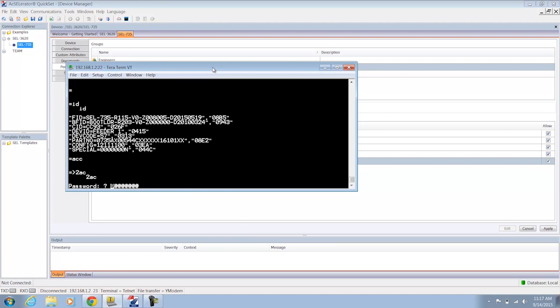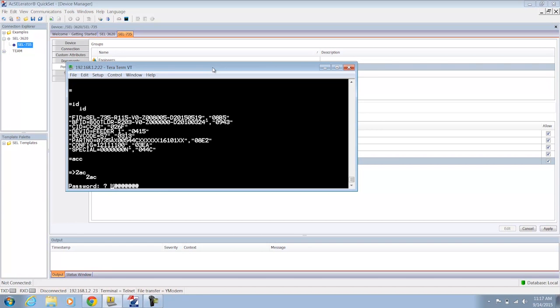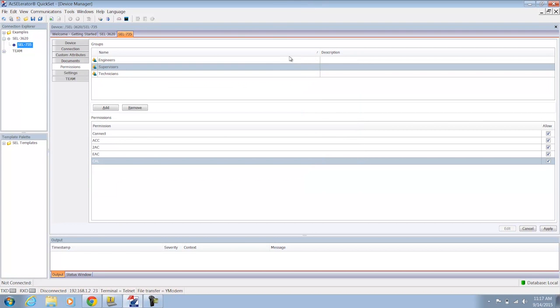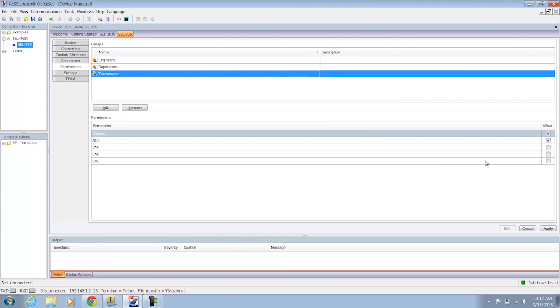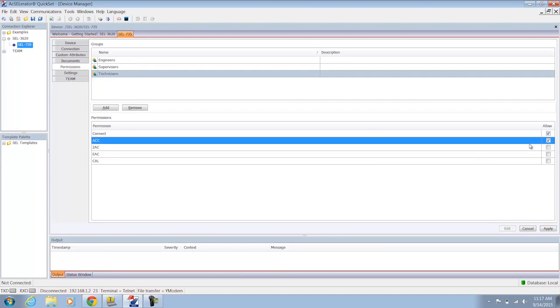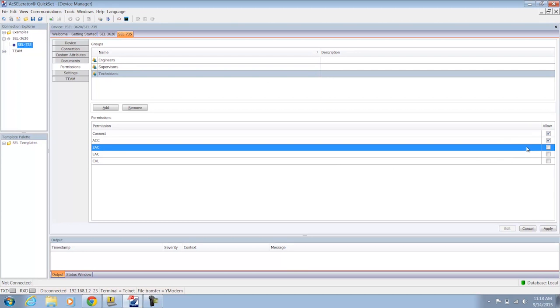I can go up to the ACC level and that password will get managed on my behalf. But if I try to go to the 2AC level it's actually going to challenge me for the password. And if I have random passwords on this device or there's some sort of strong password that's not been shared with me for this relay I won't be able to access that 2AC level on the relay. The 3620 prevents me by not entering or managing that password on my behalf. And that's because if we go back to the connection directory you'll see that I do not have access to the 2AC level of this relay.